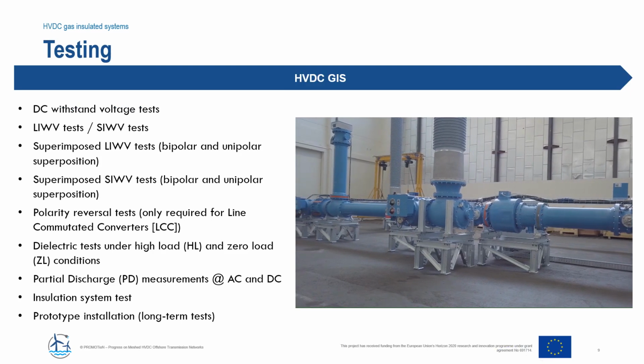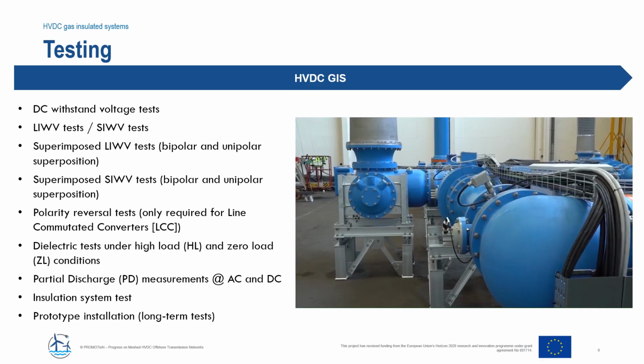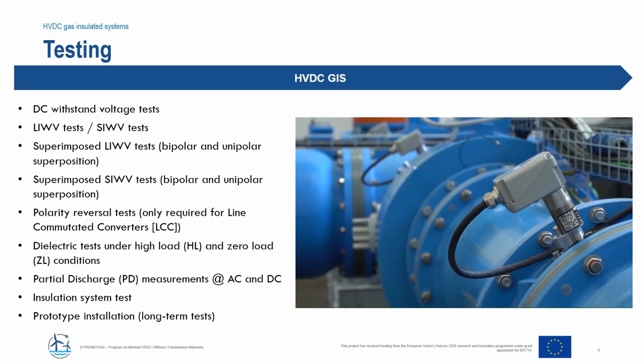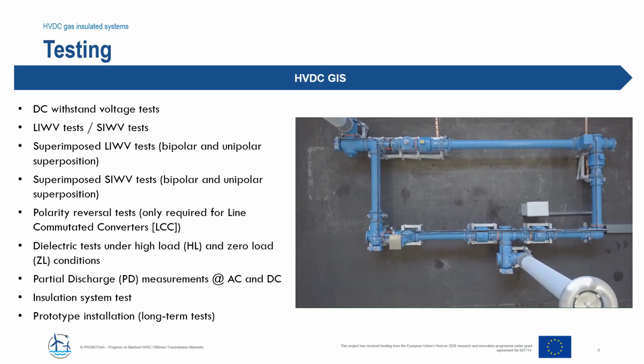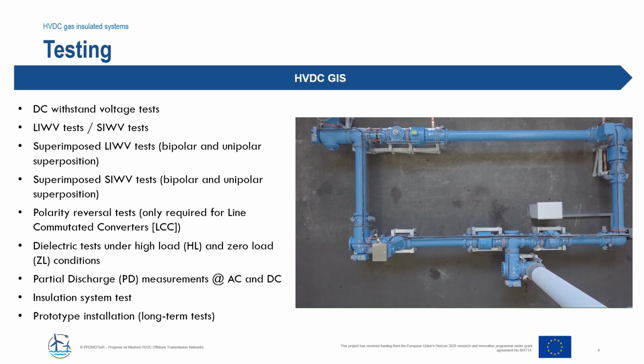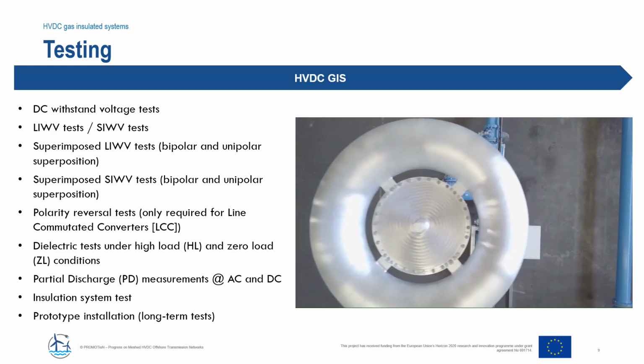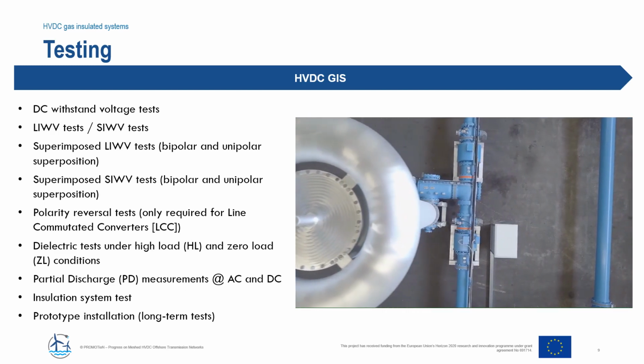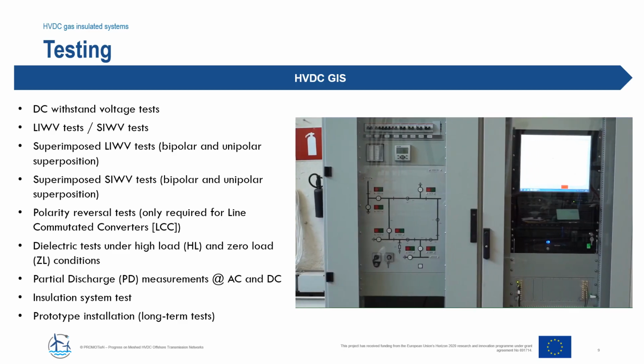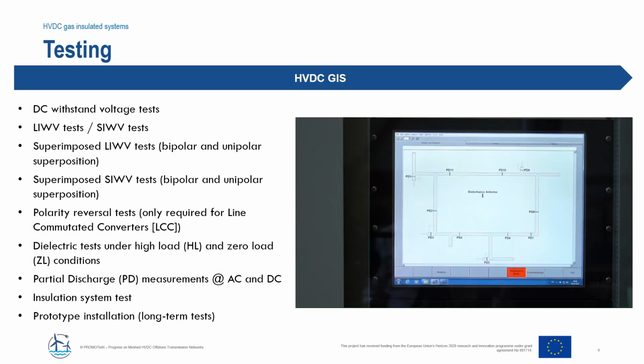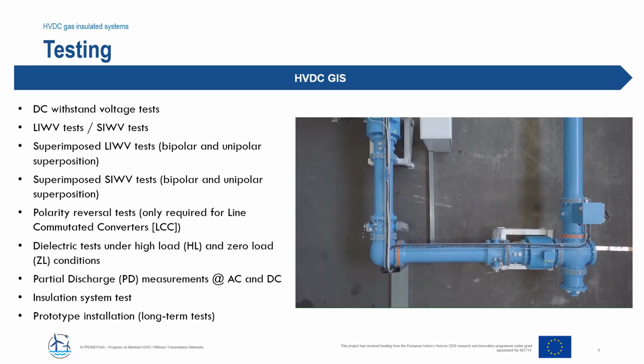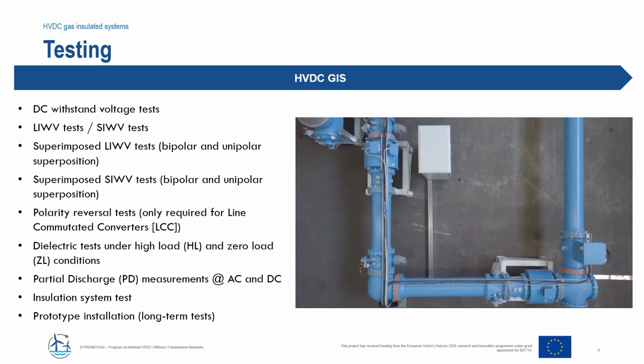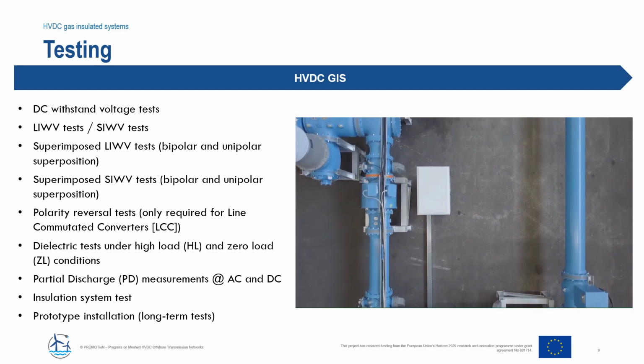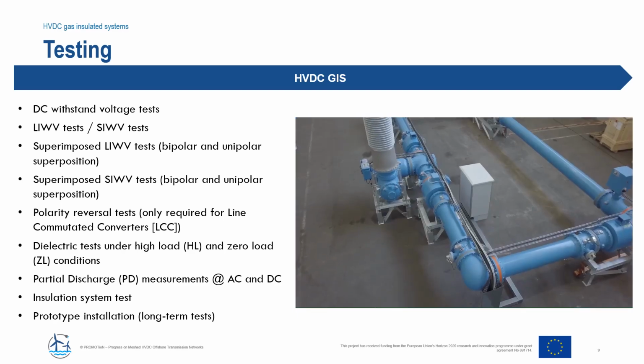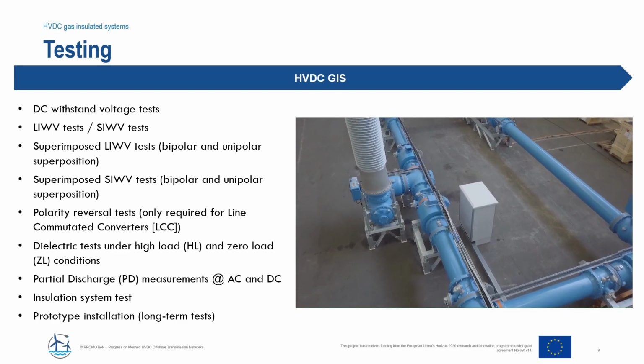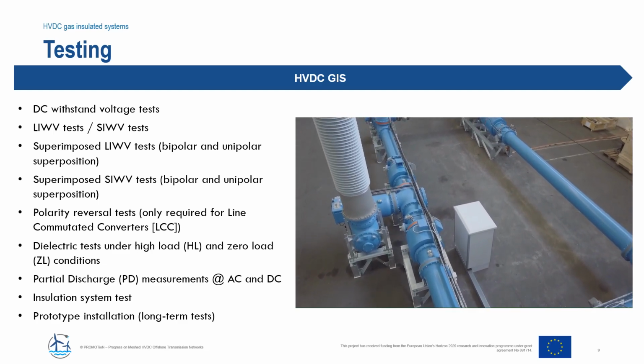Based on development and research results as well as on service experience, the manufacturer has developed new dielectric test procedures. All dielectric tests were already performed, like the DC withstand voltage tests, impulse tests, superimposed impulse tests, polarity reversal tests, dielectric tests under high load and zero load conditions, partial discharge measurement at AC and DC voltage stress. Moreover, new test procedures were developed, like the insulation system test or the prototype installation long-term test.